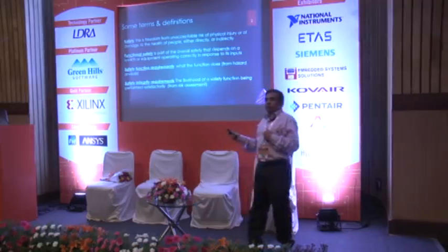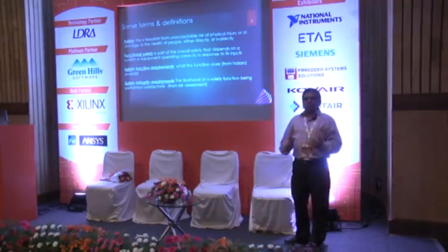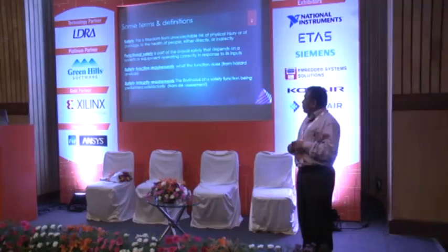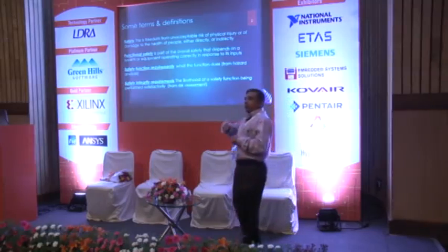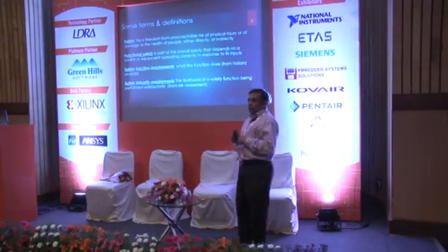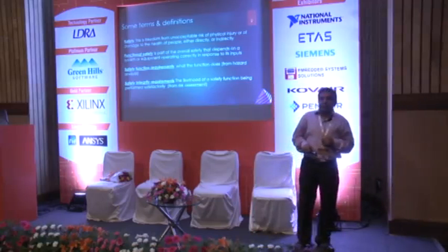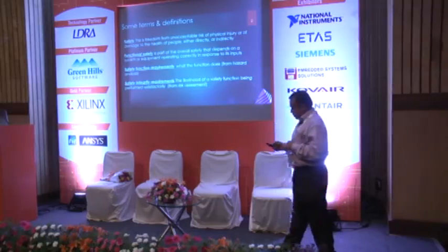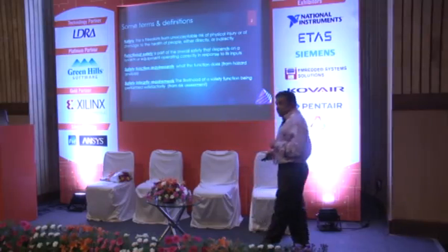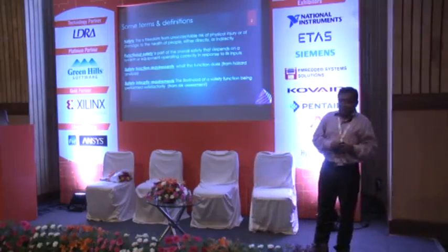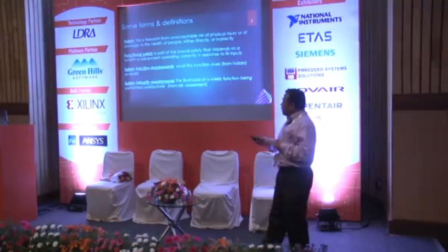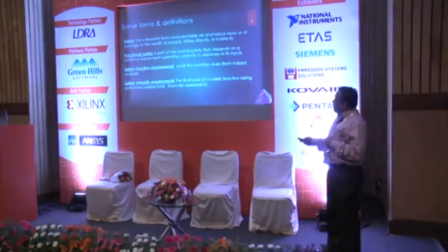Whatever you do to take care of those hazards, to minimize, reduce or eliminate them, those become the safety function requirements. And the safety integrity requirement comes from asking what if those things don't work. If there is a risk that some of those safety functions don't work, that is going to define your safety integrity levels, which comes from the risk assessment. I have planned something to take care of the hazard, and what if it doesn't work? So you have to do the risk analysis, and it results in safety integrity requirements.